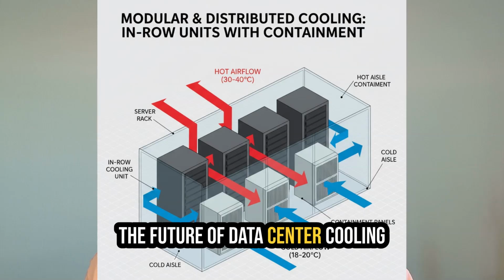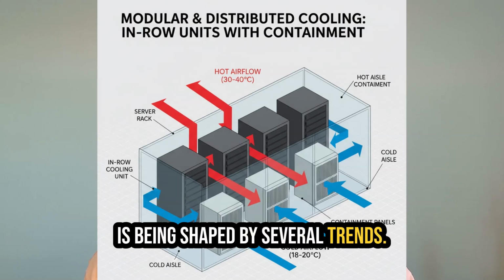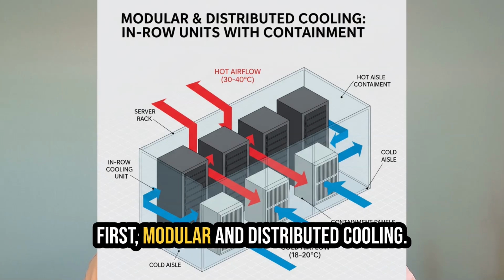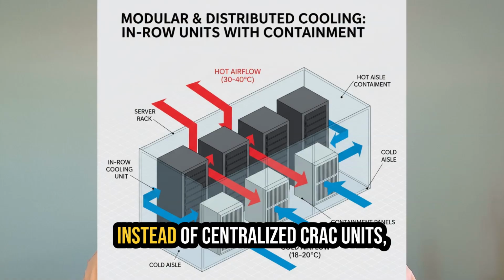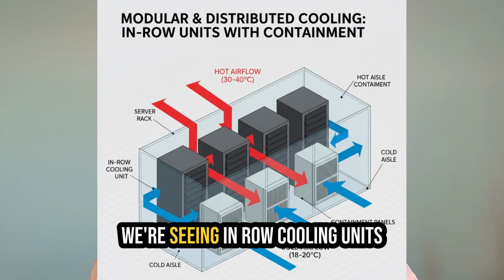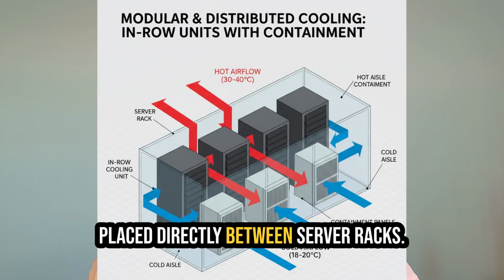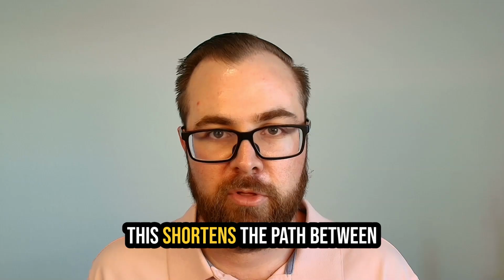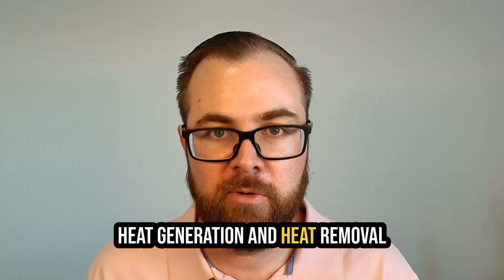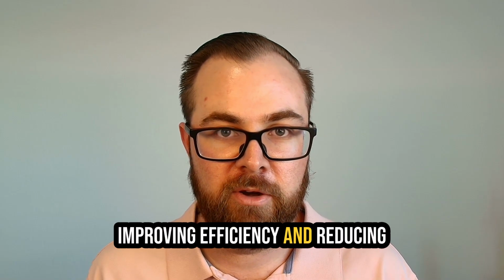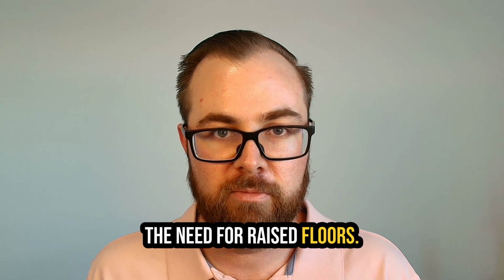The future of data center cooling is being shaped by several trends. First, modular and distributed cooling. Instead of centralized CRAC units, we're seeing in-row cooling units placed directly between server racks. This shortens the path between heat generation and heat removal, improving efficiency and reducing the need for raised floors.